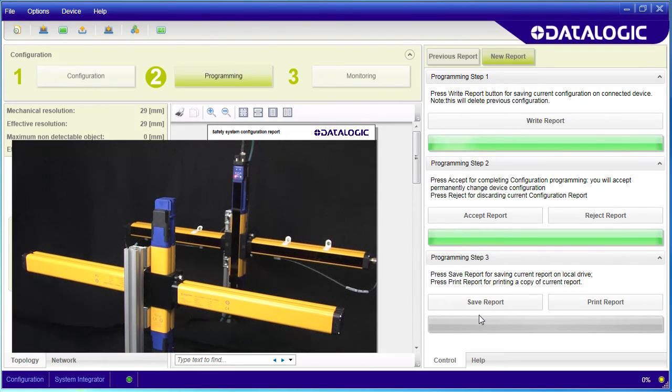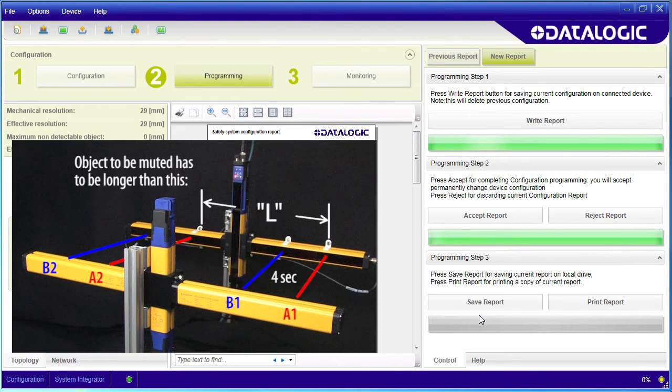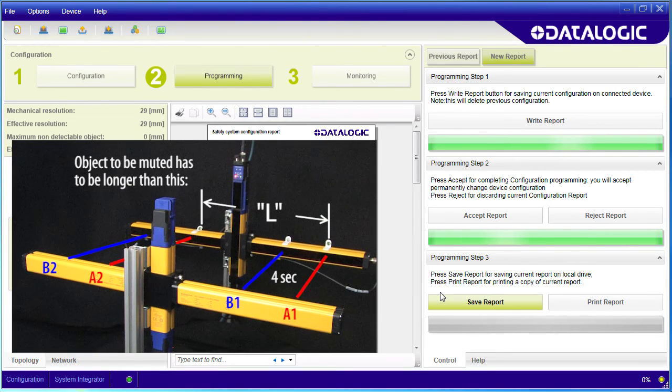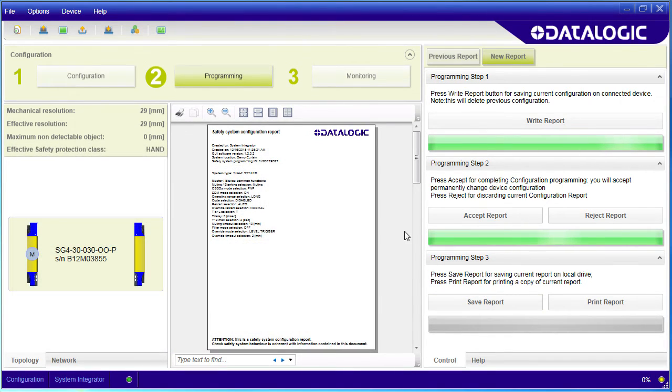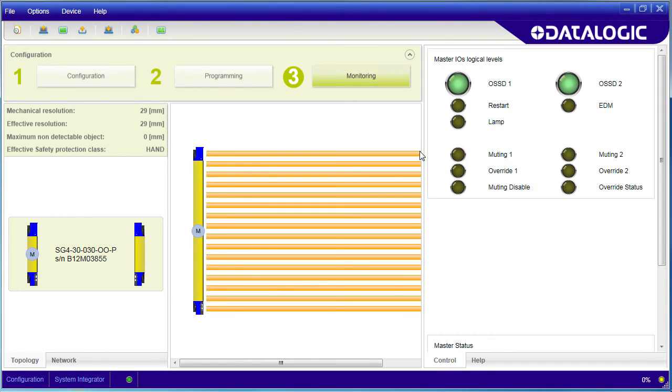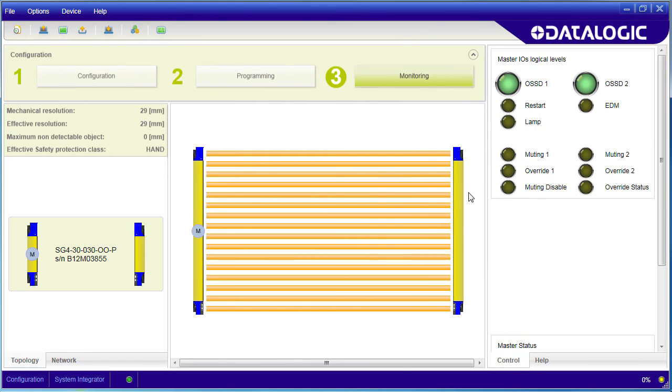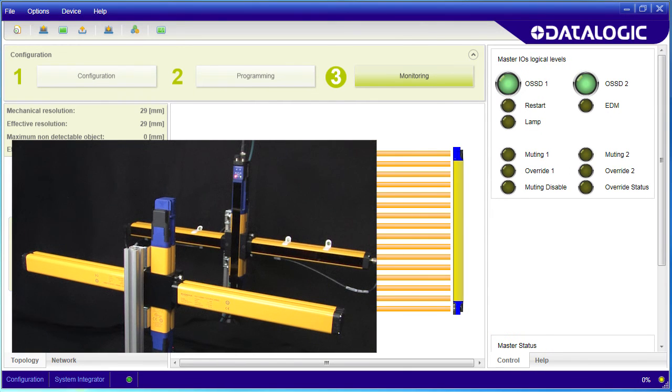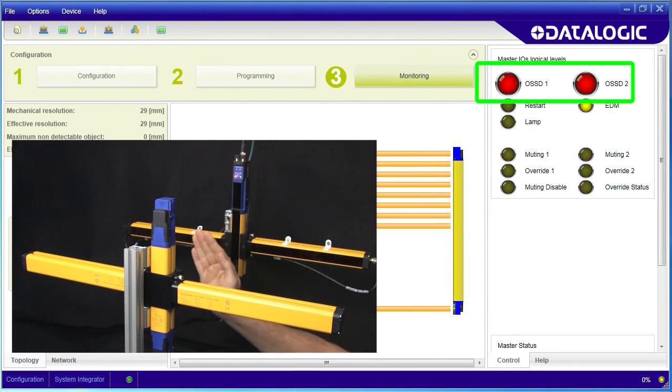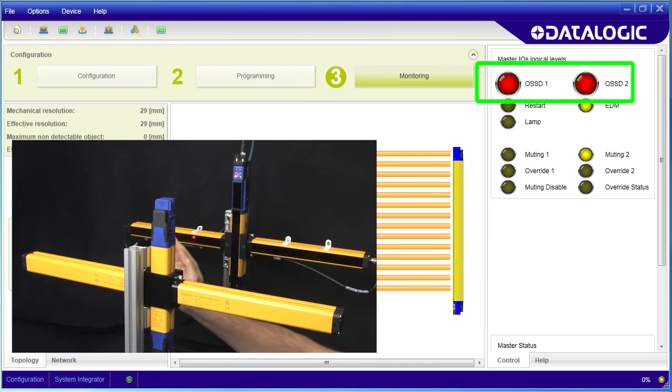The key thing to remember is the object you want to mute on has to be longer than the distance between A1 and A2 or B1 and B2. Let's switch over to the monitoring view so it can see the status lights. If I move my hand through here which is smaller than this distance, the light curtain output signal trips and shuts down the machinery.